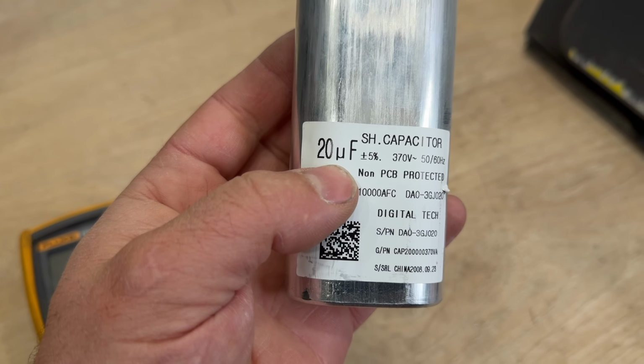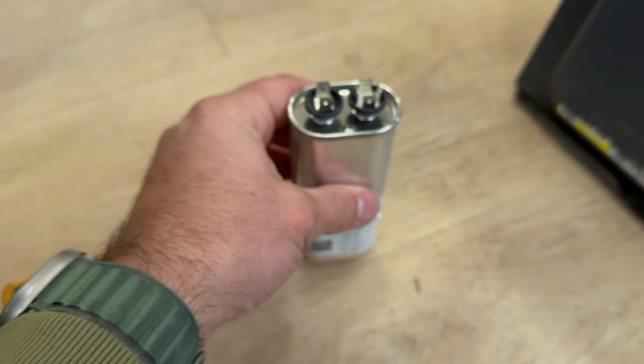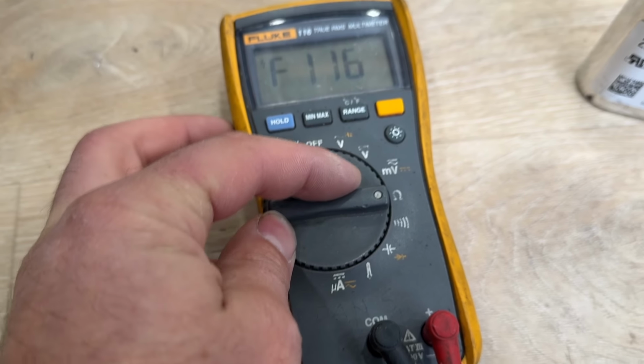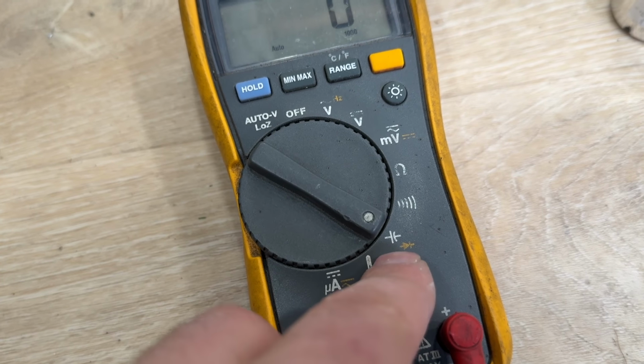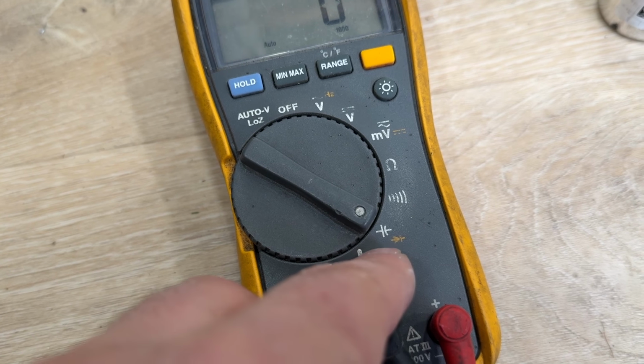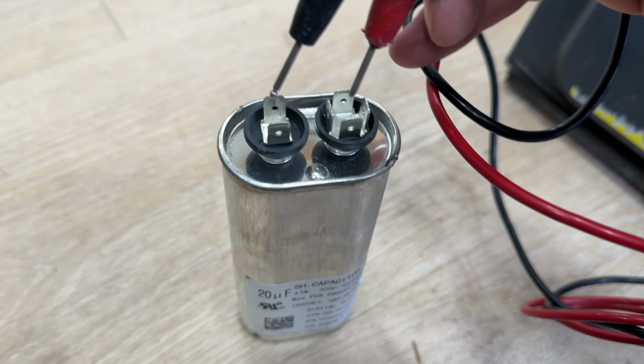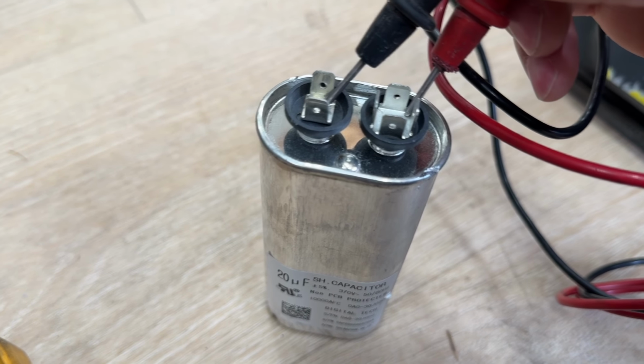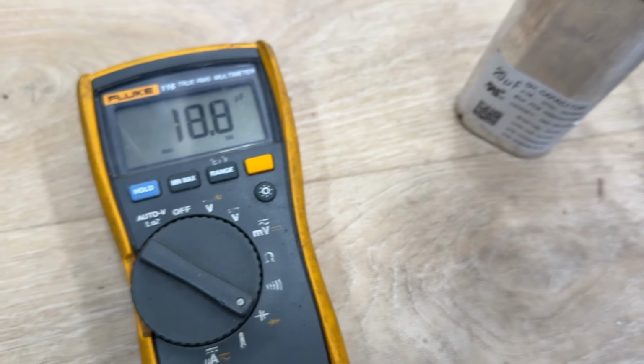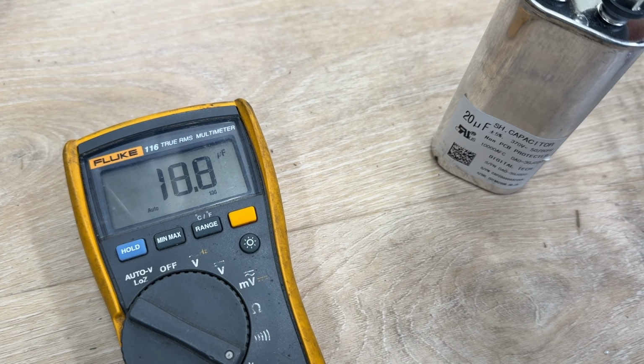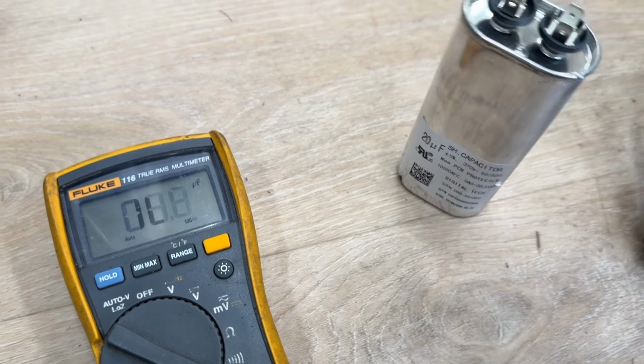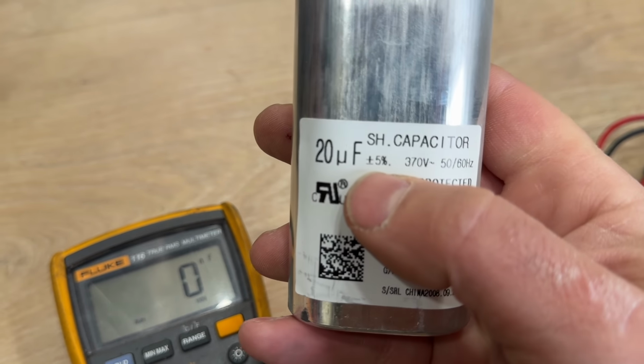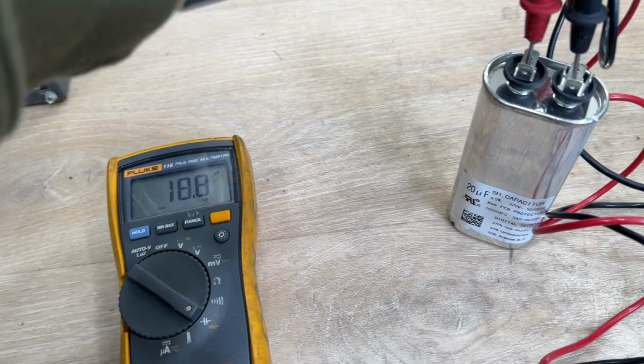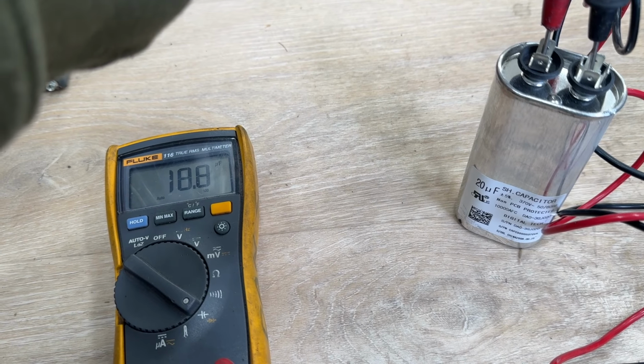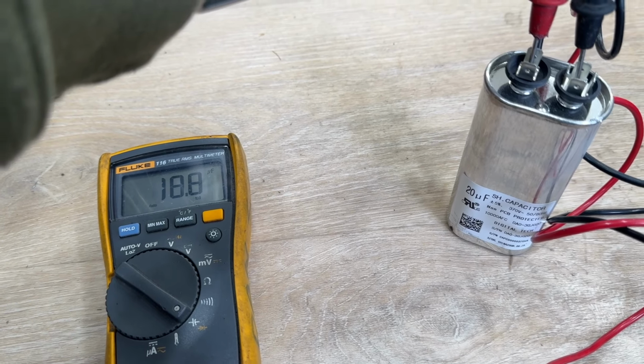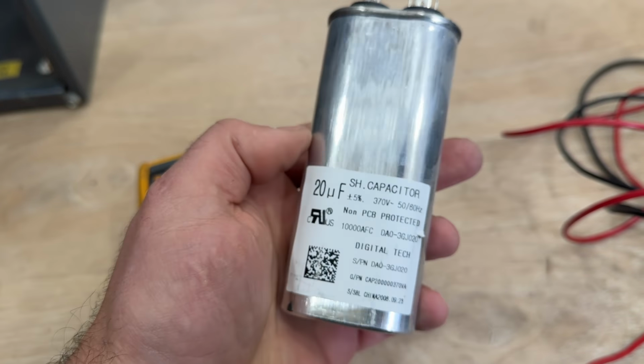Sometimes these will be a 10, a 7.5. This one in particular is a 20. So what we're gonna do is we're gonna go over to this setting right here. Looks like an arrow and a T. And then all we're gonna do is put one lead on one of these contacts and one on the other, and we'll see what our reading is. So for this guy, we have 18.8. So we're a little bit below 20, but as you'll notice right here, we have plus or minus 5%. So 5% of 20 is 1 UF. So we're actually below the threshold, and this capacitor is actually bad.